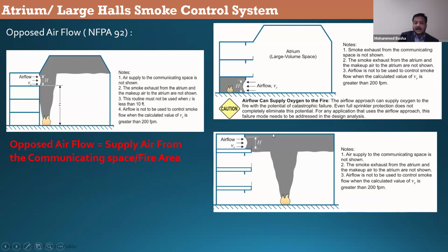So when the smoke is starting to come down, I do not want the smoke to go inside this space at first. So I'm pushing the smoke out so that the occupants in this space can come out. The occupants will be alerted at this place to come out. So this needs sound performance-based engineering calculations to have this kind of system, rather than having the mechanical smoke extract system.